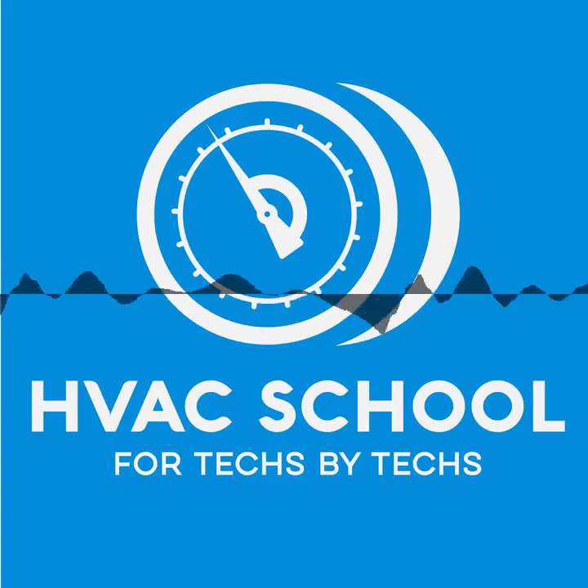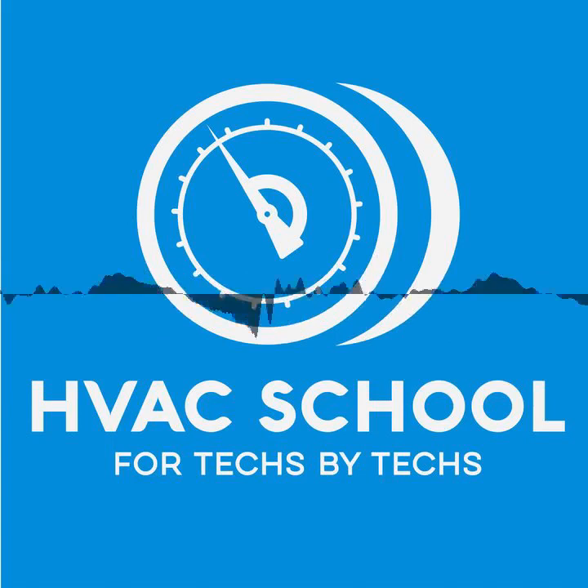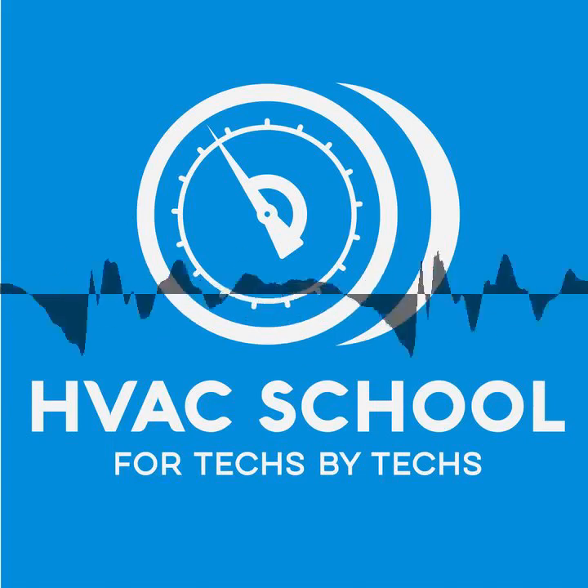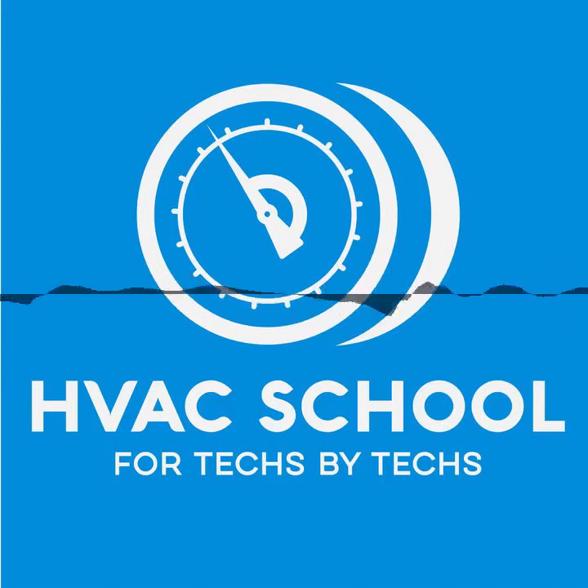You can't assume that one is going to be correct with the other, especially in circumstances where you have a vastly oversized furnace, where the furnace is much larger than the air conditioner. That can cause some real challenges. And in some cases, it's very difficult to get the airflow perfectly correct. But as a service technician in the field, you've got to be able to reference back to that manufacturer's information, and you've got to know some ways of measuring airflow if you don't have the manufacturer's information or if you have a non-standard blower device.